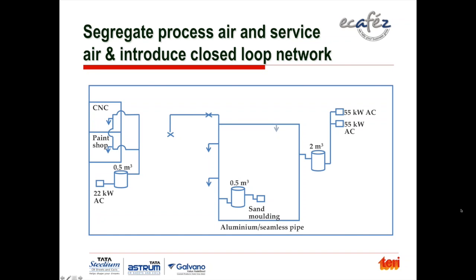This was the after situation. One of the recommendations, as you can see, was using aluminum seamless pipe instead of GI pipe, and aluminum seamless pipe leads to less pressure drop. The other thing you would have noticed in the before and after situation is a ring closed loop system. Earlier it was not a closed loop system, so they closed the loop.